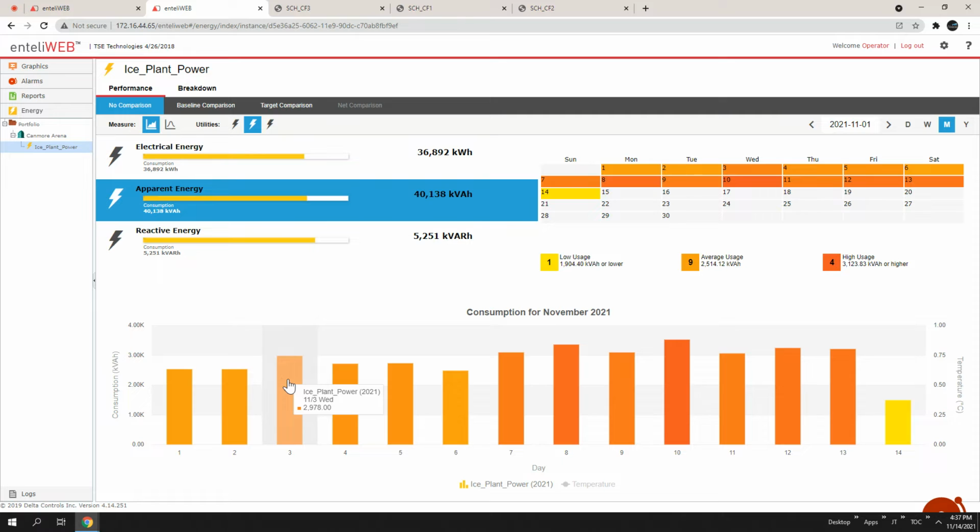Because ideally, what I'd like to do long term is compare our power use against the runtime for each pump plus the number of starts for each pump and each compressor, and essentially be able to work out different ways of setting the ice set points and the differential, like the delay on the pump, whether it's going to start half a degree off, and work with the operators and try and get our power use down as low as possible, essentially.